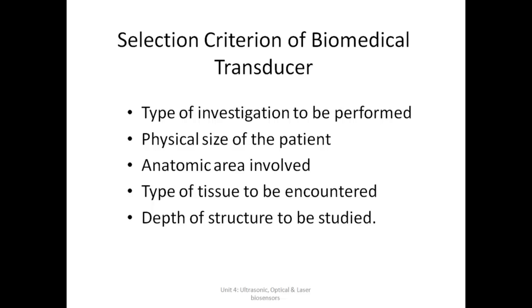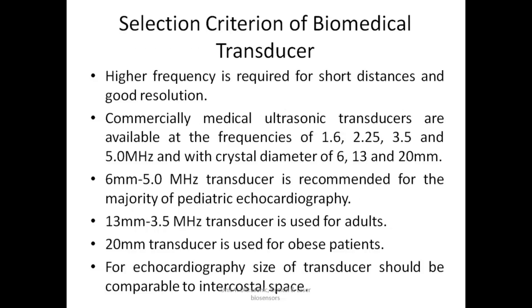Depth of the structure that is to be studied matters because, like you have already seen, there is something called attenuation, something called half value layer. That means as your wave is propagating through a medium, the signal also gets lost. So up to what depth we want to measure, up to what depth the structure has to be seen or imaged, according to that we have to select how much frequency signal we need to incident on the particular area. Higher frequency is required for short distances and good resolution.